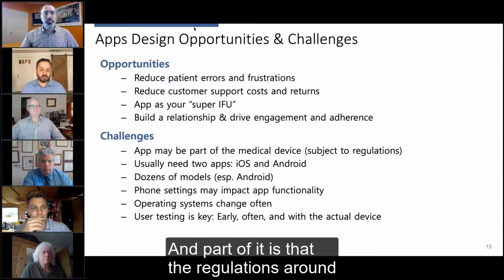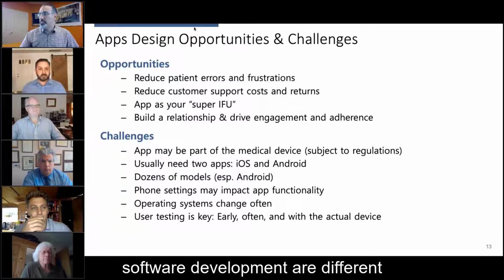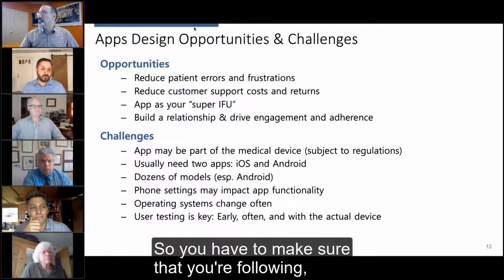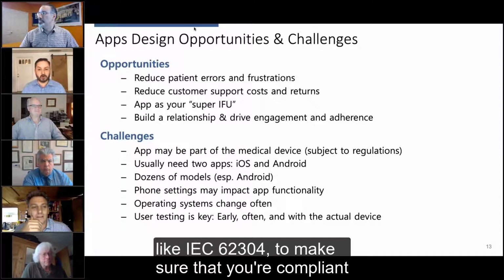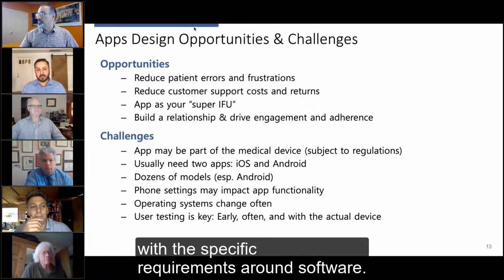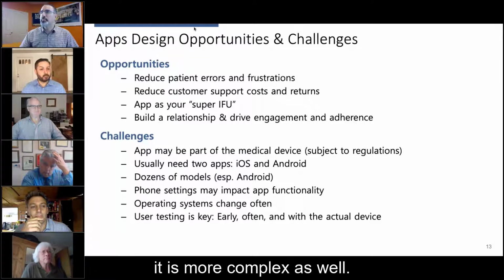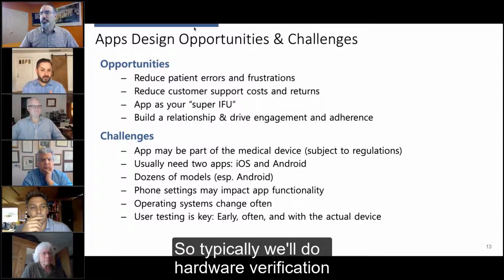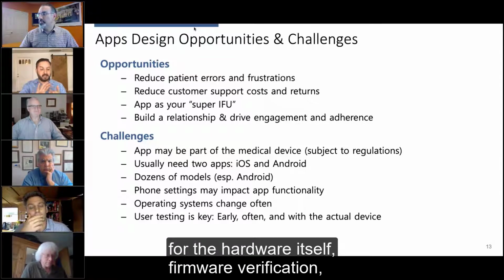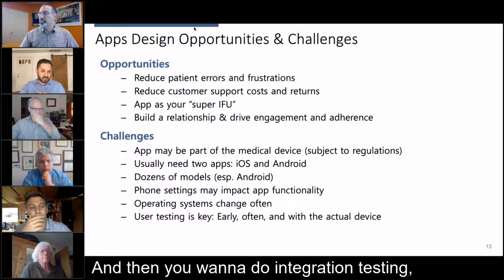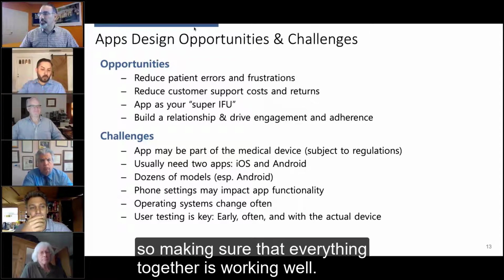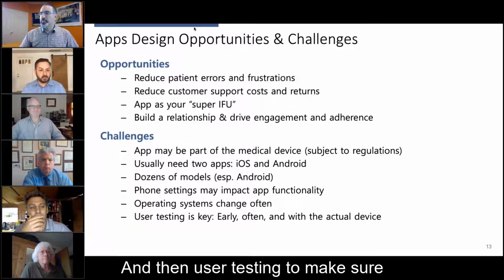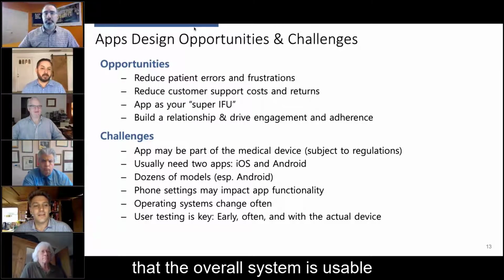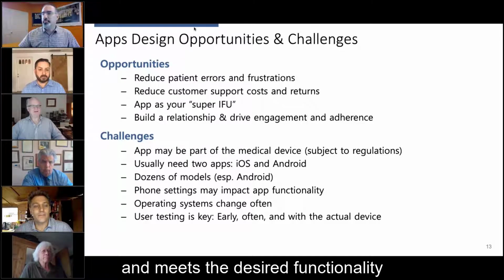And part of it is that the regulations around software development are different than the types of things that you have to do for hardware. So you have to make sure that you're following IEC 62304, to make sure that you're compliant with the specific requirements around software. And then on the verification side, it is more complex as well. So typically we'll do hardware verification for the hardware itself, firmware verification, app verification, and then you want to do integration testing. So making sure that everything together is working well, and then user testing to make sure that the overall system is usable and meets the desired functionality or the intended use.